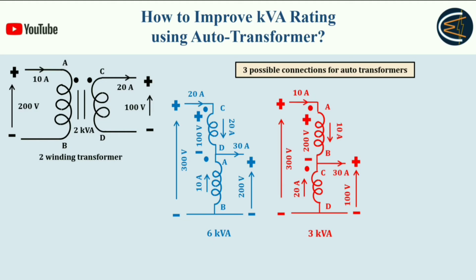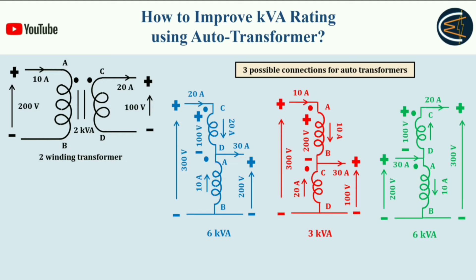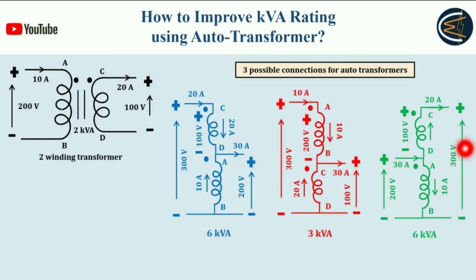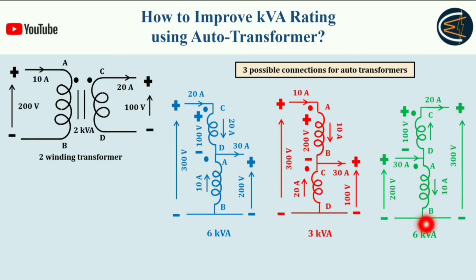Here also you are getting a higher KVA compared to the two-winding transformer, which is 2 KVA. Now for the last possible connection: the CD winding is placed here and the AB winding here, with the primary side being 200 volts applied across A and B. The secondary side is taken between terminals C and B. Across the secondary side we get 300 volts — because AB winding has a rated value of 200 V and CD winding 100 V, giving 300 V total. Calculating gives 6 KVA as the power rating.